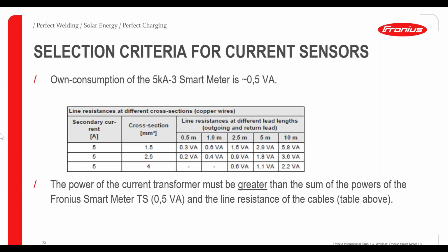We have a table here for the selection criteria of the correct current sensors. When you are choosing the current transformers, there are 2 things you need to keep in mind. The first important thing is the own consumption of this commercial smart meter, the 5 kiloamp smart meter, which is about 0.5 volt-amperes. The second thing is the length and the cross section of the cable between the smart meter and the current transformers. The power of the current transformer must be higher than the sum of the power of the Fronius smart meter, which is 0.5, and the line resistance of these cables.